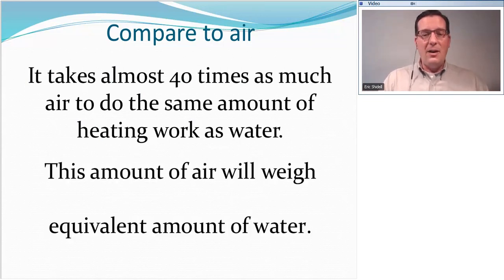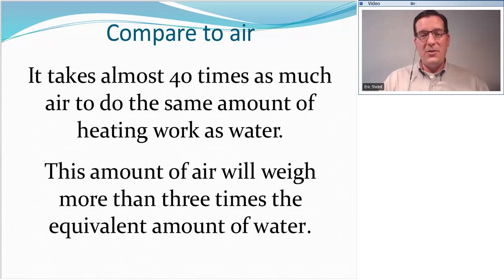It takes almost 40 times as much air to do the same amount of heating work as water. And this fact brings us specific advantages to the hydronic side of things. One of those advantages has to do with the fact that this amount of air will literally weigh 3 times more than the equivalent amount of water when it comes to heat transfer. So pound for pound, hydronic heating is more effective. We need to move a lot more air than we do need to move water. And that air actually weighs 3 times as much as the water does, which means it takes a lot more energy to move that air, to use fan energy.